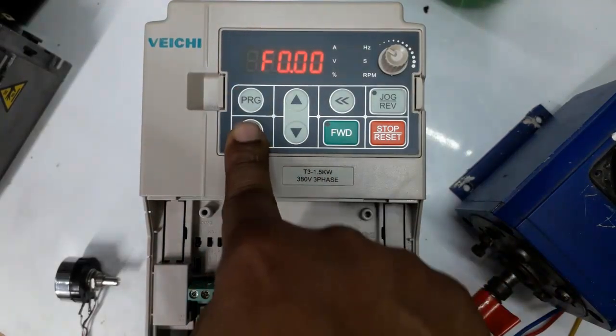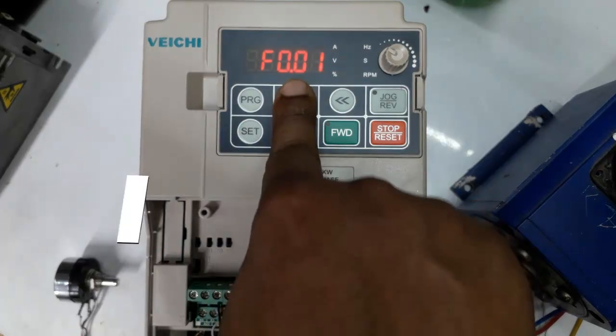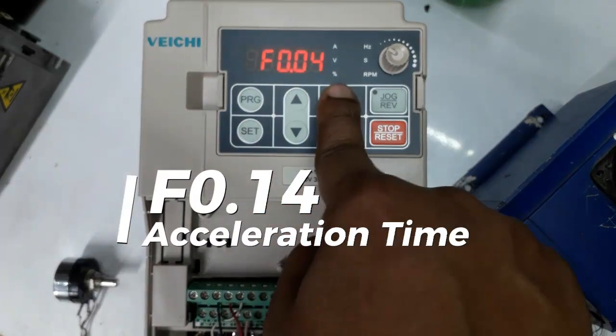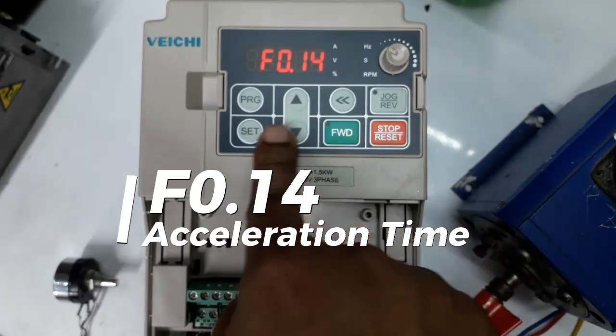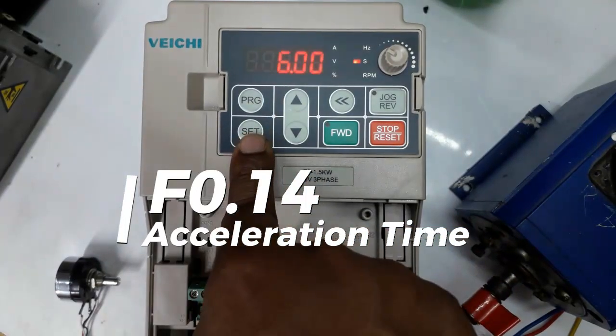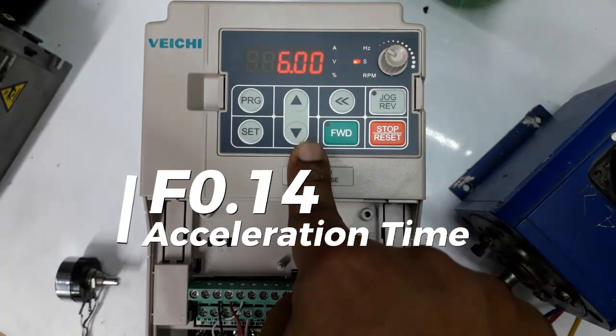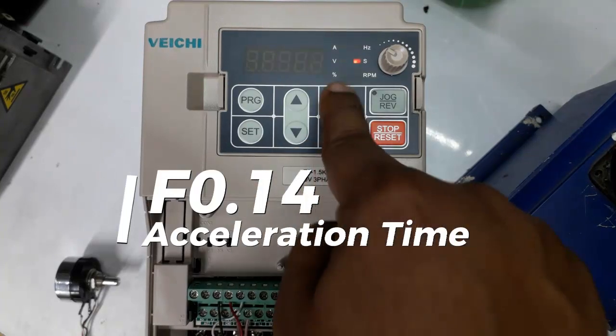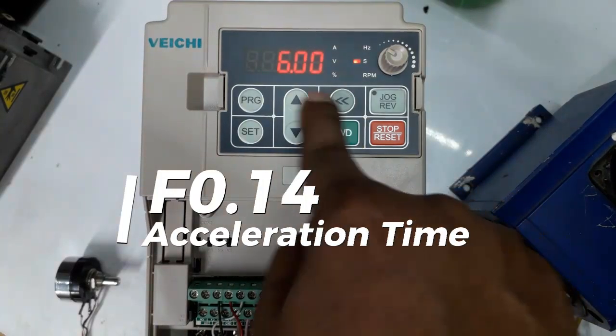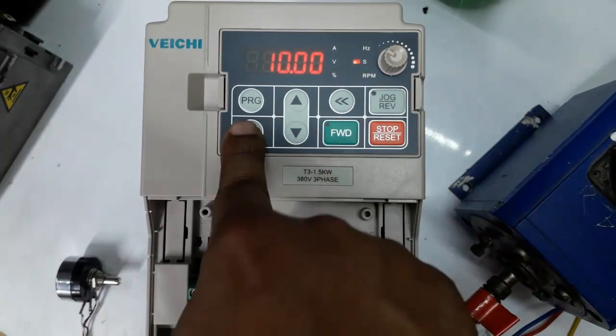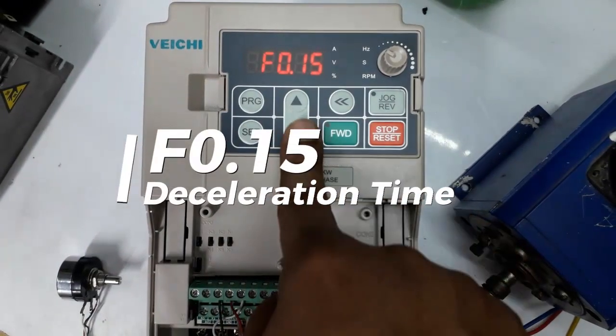Acceleration and deceleration setting in the drive. For acceleration time setting, the parameter is F0.14. The default setting is 6 seconds. You can set the acceleration time and deceleration time as per your machine requirement.